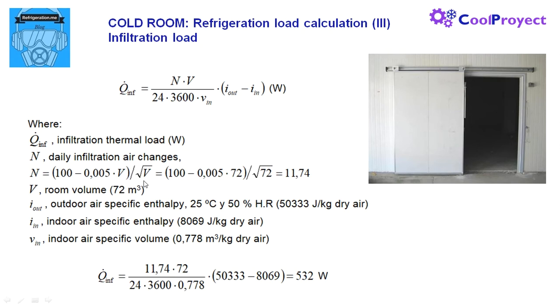The result is 11.74 but imagine our room is about 1000 cubic meters, then the daily air changes are about 3. That is to say, the more room volume the less air change when opening the doors. Makes sense doesn't it?